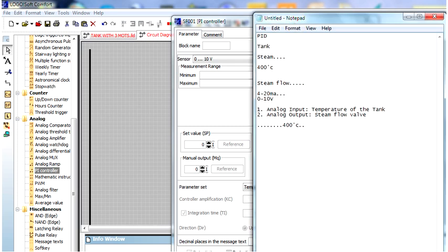You know, if you watch my previous video about the PLC analog system, there is an engineering value and a voltage or current signal. The engineering value is sometimes 0 to 27,648 for standard PLCs, but for this Siemens Logo PLC the engineering value is 0 to 1000. The higher the value range, the more precision you will get.